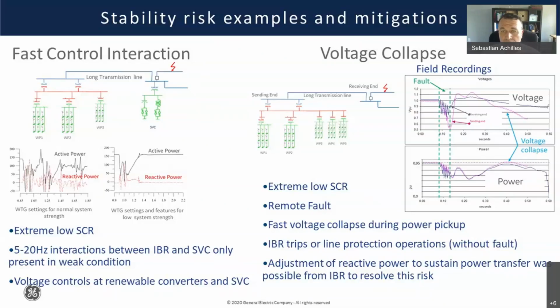So you can see the recordings. On the right of the picture, there is one that says voltage. Those are voltages on the sending and receiving end. Sending end will be the voltage on the wind plant side of the long transmission line, and receiving end is the opposite side. And then in the lower plot, you see the power. Both of them are kind of the same because the losses in the line are relatively low.